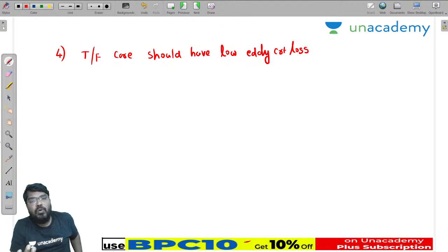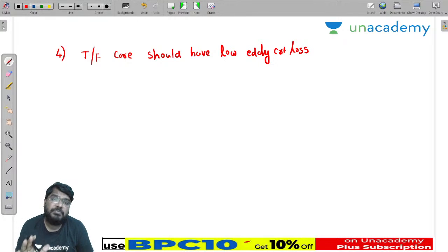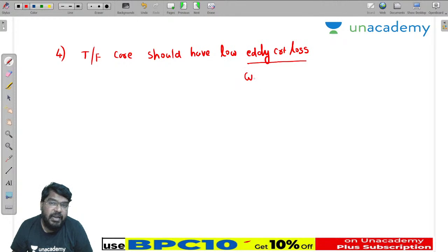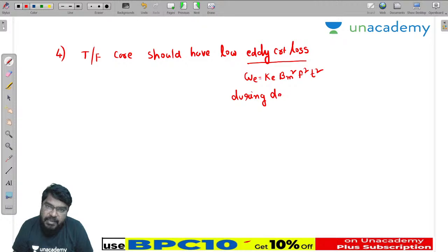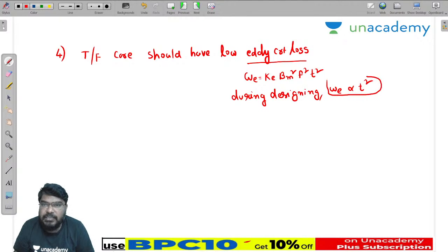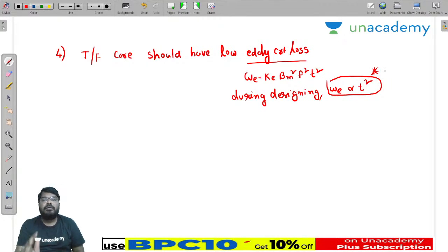As the losses are low, you can improve the efficiency of the transformer. So the desirable properties of the core are low hysteresis losses and also low eddy current losses. What is the formula for eddy current losses? Eddy current loss is equal to some constant Ke, times B maximum square, f square and t square. So during the designing or manufacturing of the transformer, this eddy current loss is directly proportional to the square of the thickness of the laminations.